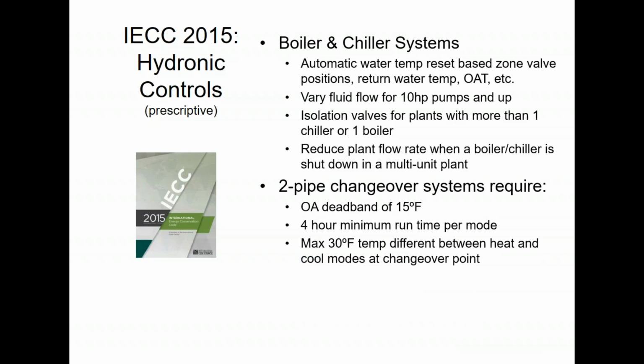If you have two-pipe systems, which I'd highly recommend you avoid, but some buildings already have them, so you're retrofitting them, so it is what it is. Sometimes you'll see these in mid-rise and high-rise condos that have chilled water and hot water. And the condo, they kind of figure out there's not a lot of cooling load compared to a commercial building. Maybe we can get away with it. People complain in the spring and fall for a couple weeks, and then they forget about it, right?